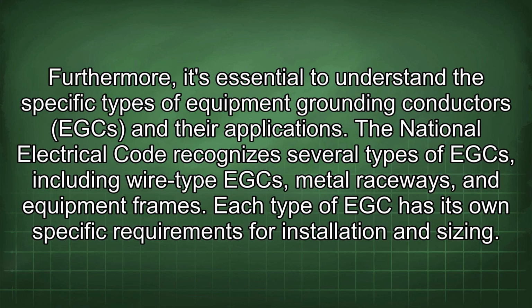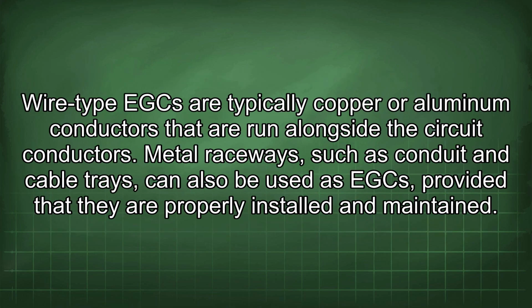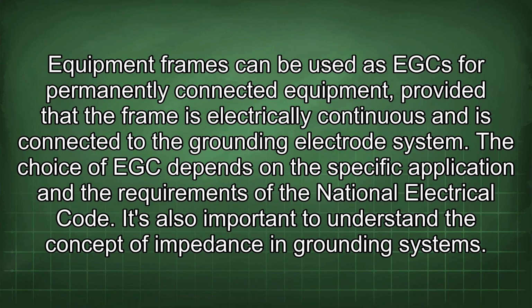Furthermore, it's essential to understand the specific types of equipment grounding conductors, EGC, and their applications. The National Electrical Code recognizes several types of EGC, including wire-type EGC, metal raceways, and equipment frames. Each type of EGC has its own specific requirements for installation and sizing. Wire-type EGC are typically copper or aluminum conductors that are run alongside the circuit conductors. Metal raceways, such as conduit and cable trays, can also be used as EGC provided that they are properly installed and maintained. Equipment frames can be used as EGC for permanently connected equipment, provided that the frame is electrically continuous and is connected to the grounding electrode system. The choice of EGC depends on the specific application and the requirements of the National Electrical Code.